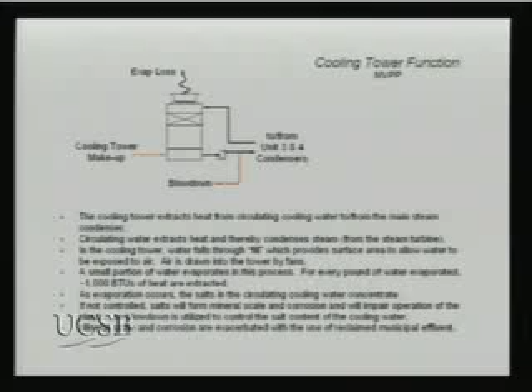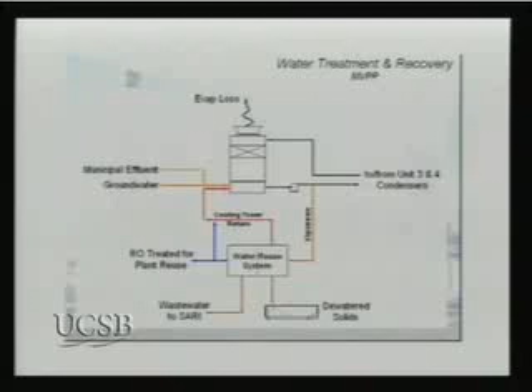The plant has inserted in the cooling circuit a water reuse system. What it does is it takes what is known as a slipstream. It takes a little bit of the water that's circulating around and around the cooling towers, and it treats it. It has basically 2 levels of treatment. The first is just basic minerals removal: calcium, magnesium, a little bit of silica. And then the second phase is really the desal piece. That little dashed line in the middle of that box distinguishes those 2 phases. Now, if we didn't have this plant, the blowdown would be much, much greater. The waste stream would be much, much greater.